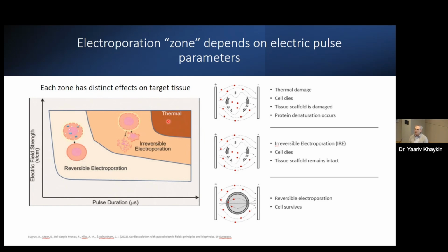And it turned out that you can fine-tune this energy delivery specific to the electrodes that you're using, the electrode configuration, electrode size. You can deliver it in a monopolar, bipolar, monophasic, or biphasic pattern, and 2 trains, 5 trains, 10 trains, however which way, with different frequencies between the trains, in order to specifically target different tissues.